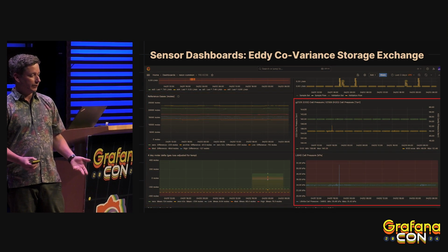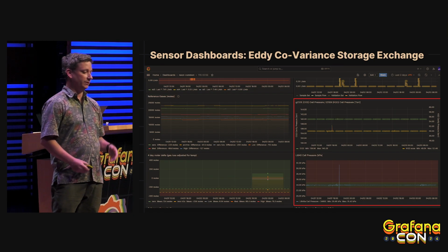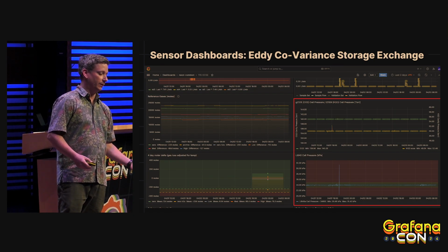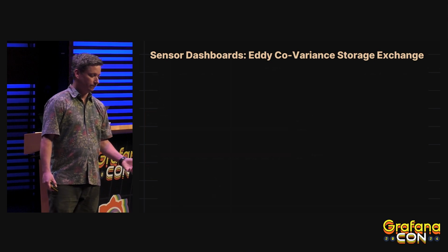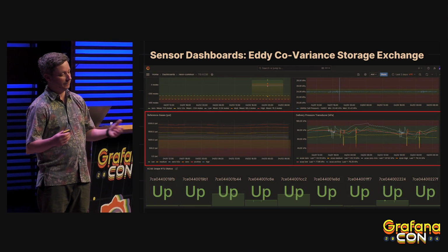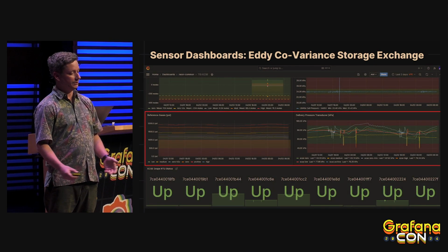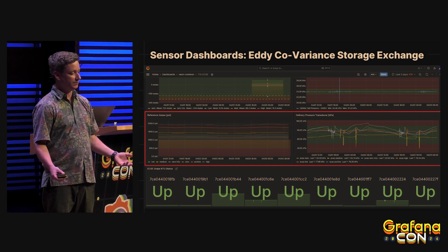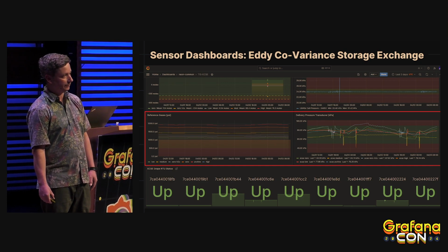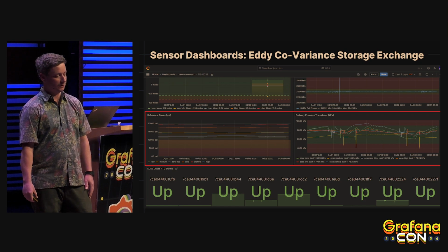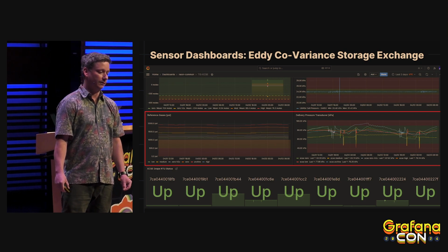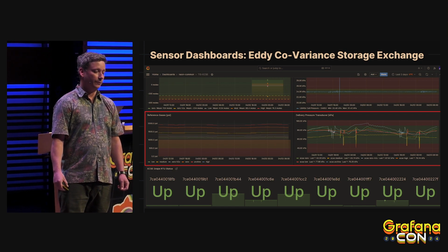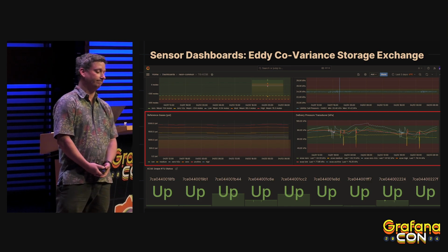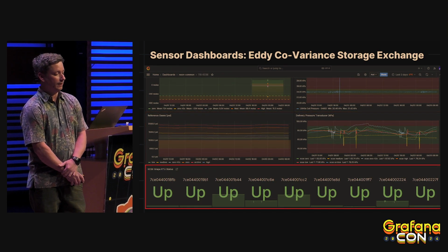On the right here, we have pressure readings from all the gas analyzers with expected thresholds and set points visualized on the same graph. And finally, at the bottom of this dashboard, we have unadjusted gas loss on the left, which you can see is a bit wavy with temperature variations throughout the day, and the delivery pressure of all those cylinders on site from their regulators plumbed to the instruments.